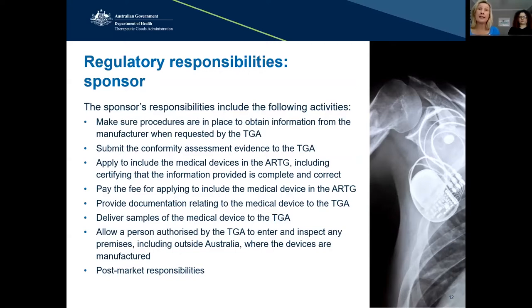If we ask for any samples, the TGA may choose to undertake some testing of devices, and they need to be provided. The TGA can also enter any manufacturing premises, both inside or outside of Australia. The sponsor also has post-market responsibilities around maintaining records of distribution and knowing where they're supplying their products to.